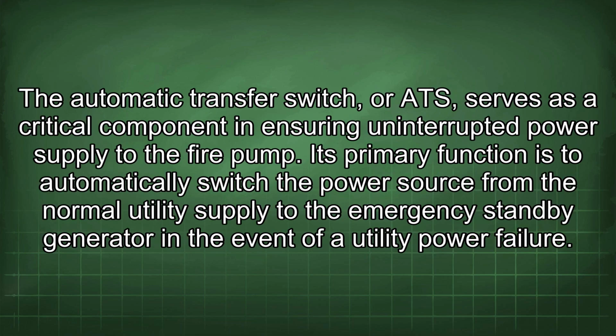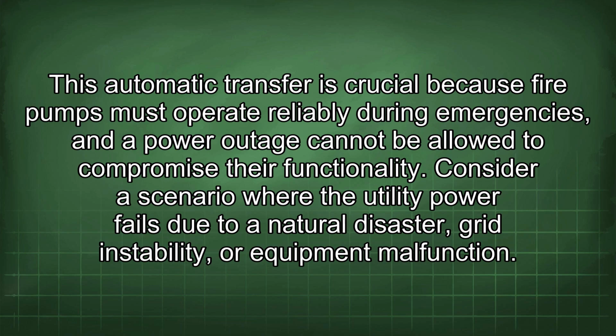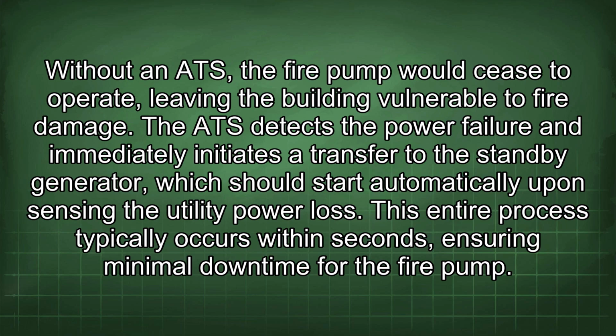The automatic transfer switch, or ATS, serves as a critical component in ensuring uninterrupted power supply to the fire pump. Its primary function is to automatically switch the power source from the normal utility supply to the emergency standby generator in the event of a utility power failure. This automatic transfer is crucial because fire pumps must operate reliably during emergencies, and a power outage cannot be allowed to compromise their functionality. Consider a scenario where the utility power fails due to a natural disaster, grid instability, or equipment malfunction. Without an ATS, the fire pump would cease to operate, leaving the building vulnerable to fire damage.